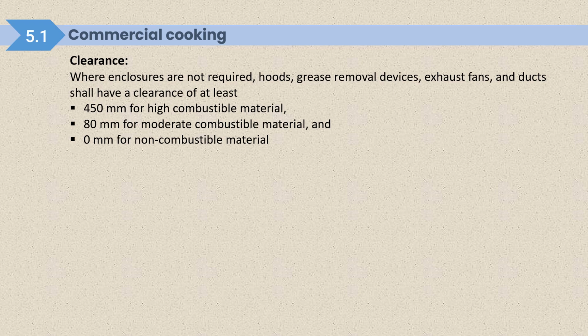In the hood and exhaust system, you will see clearance guidelines given where enclosures are not required. We will see the enclosures in the next slide. We have given one layout where you can get the exact idea of what the enclosure is. Hoods, grease removal devices, exhaust fans and ducts shall have a clearance of at least 450 mm for high combustible material, 80 mm for moderate combustible material, 0 mm for non-combustible material.